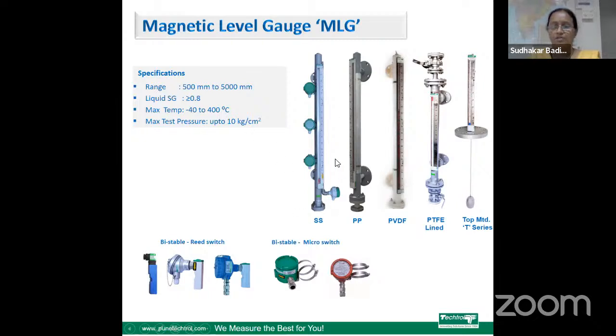So on the right hand side, you can see the various level gauges in different MOCs. This is the SS level gauge. This is the gauge in PP, then in PVDF. This is PTFE lined, and this is the top mounted level gauge. On the bottom side, you can see the bistable switch, which uses reed switches, and this bistable switch, which uses micro switches.